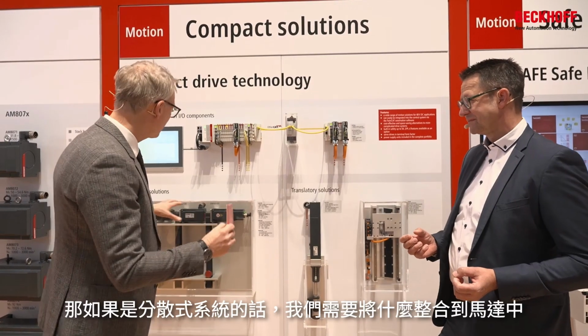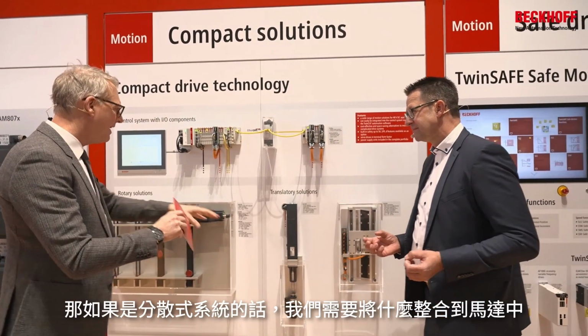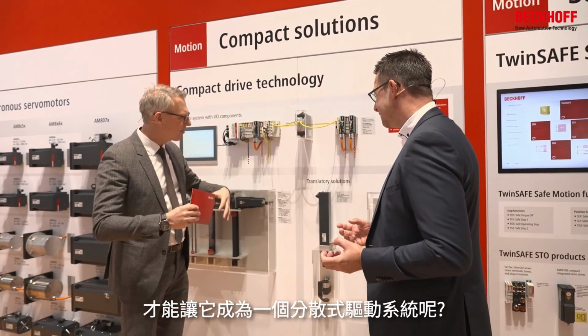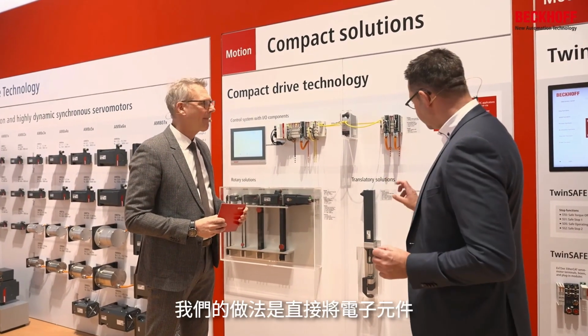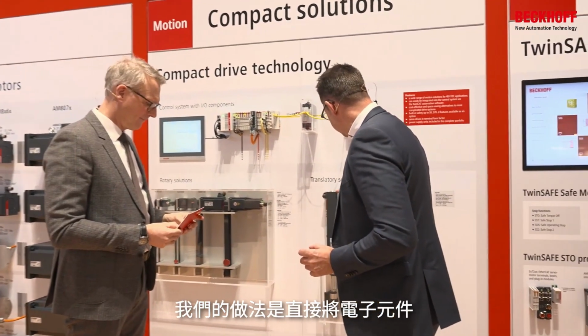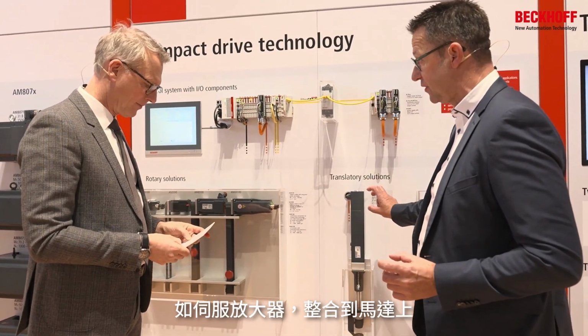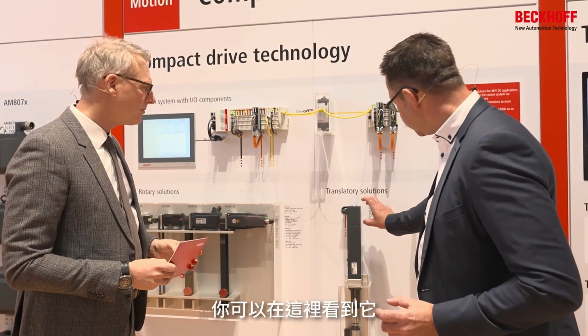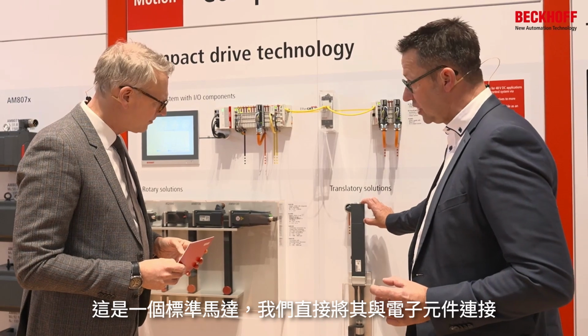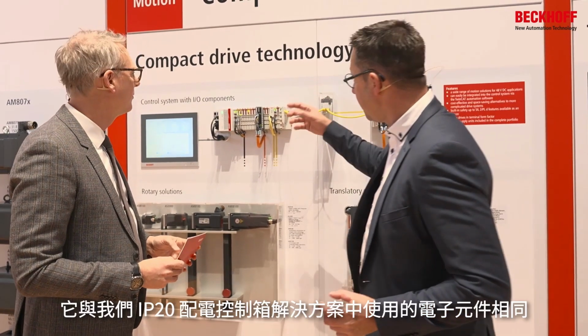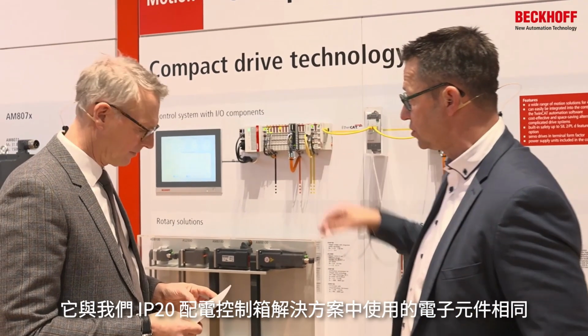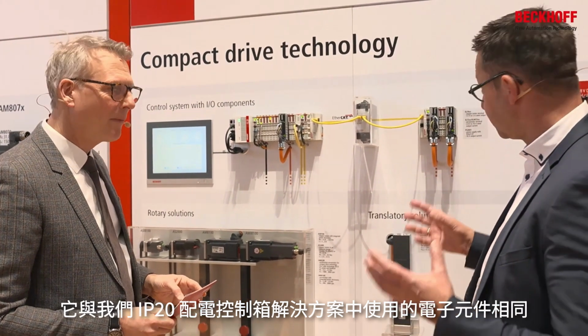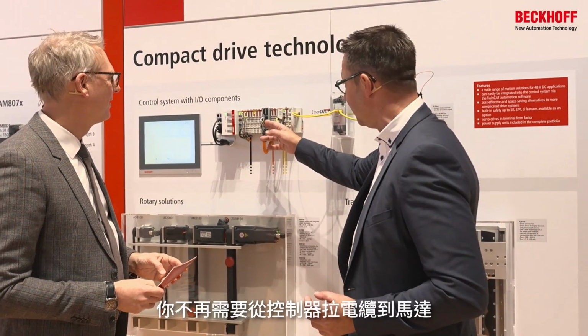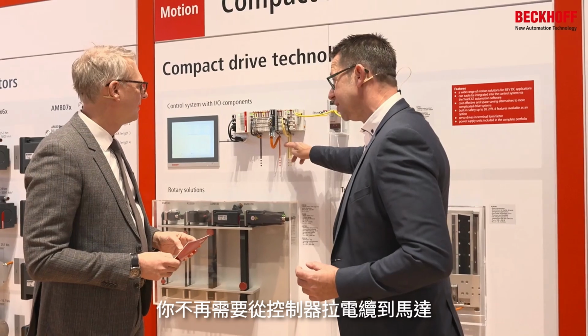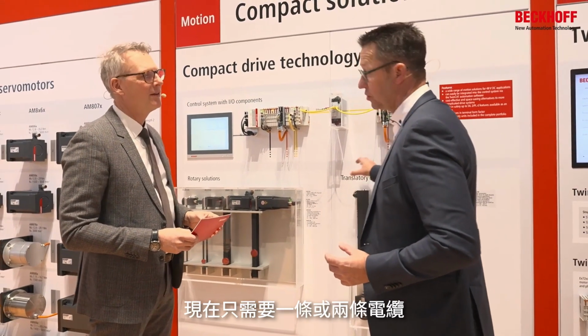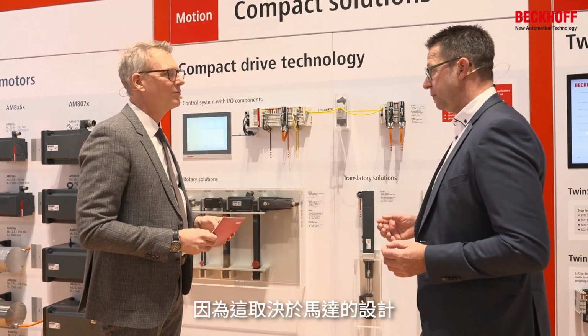Okay. Now, if it's decentral, what do we need to integrate into the motor to make it a decentralized drive system? Yeah, what we are doing is that we put the electronics, so the servo amplifier, for example, directly onto the motor. You see it here. This is a standard motor, and we attach the electronic directly. It's the same electronic we use here in our IP20 solutions for the switch cabinet. And you see what is missing? You don't need the cable from the controller to the motor because you only have one or two cables, depends a little bit, to the motor.